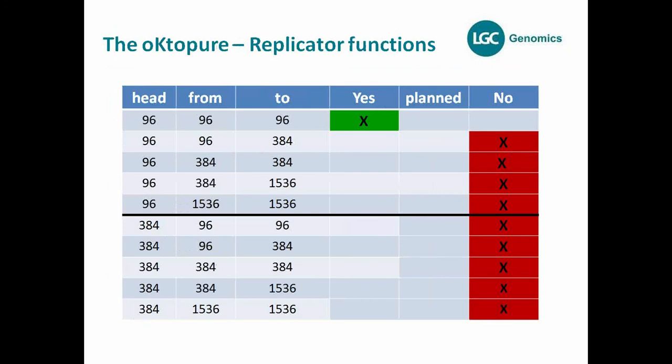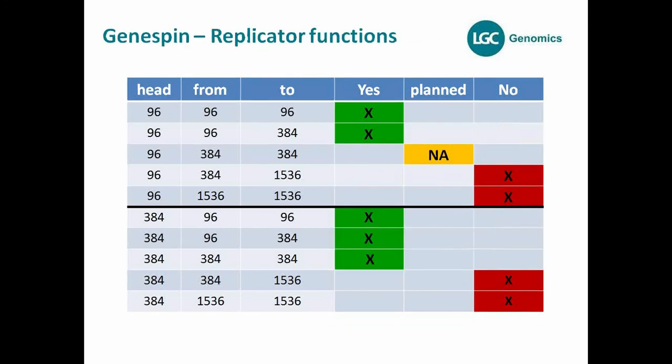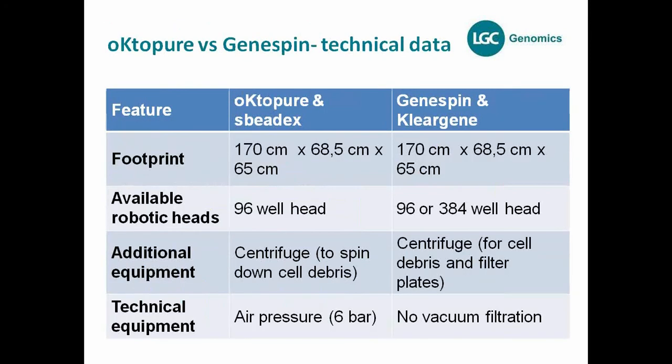To summarize: oKtopure has low consumable costs, high throughput, but no replicator functions — you can only pipette in 96-to-96 format. GeneSpin has replicator functions including 96-to-384, and with a 384-head option even further options are available in the future. Both systems lack replicator functions in certain respects, but GeneSpin has more flexibility here.